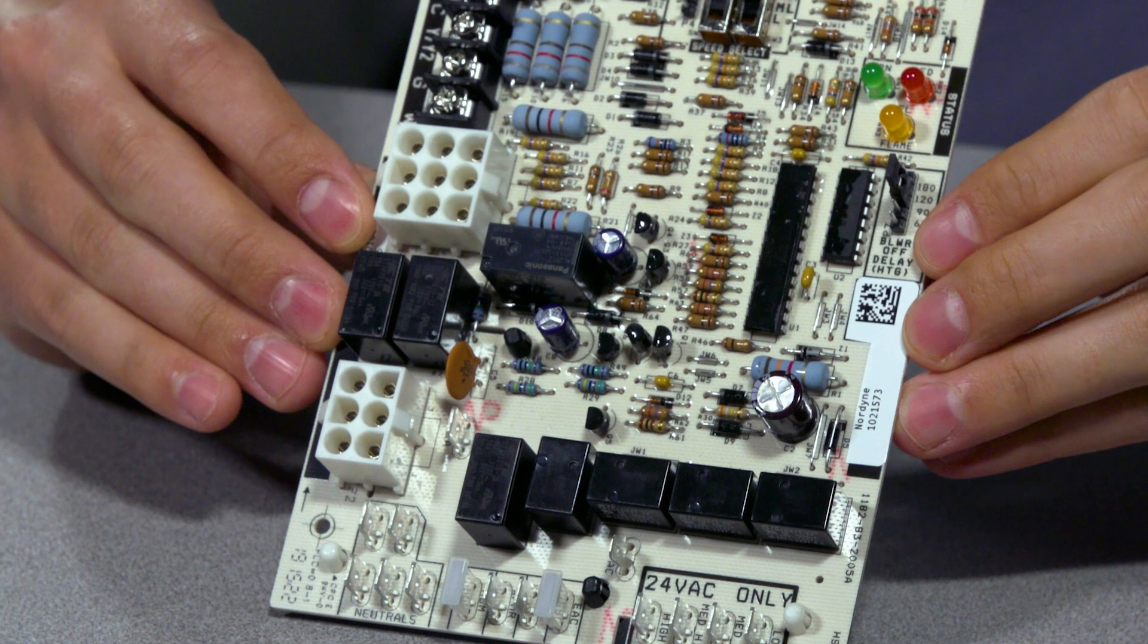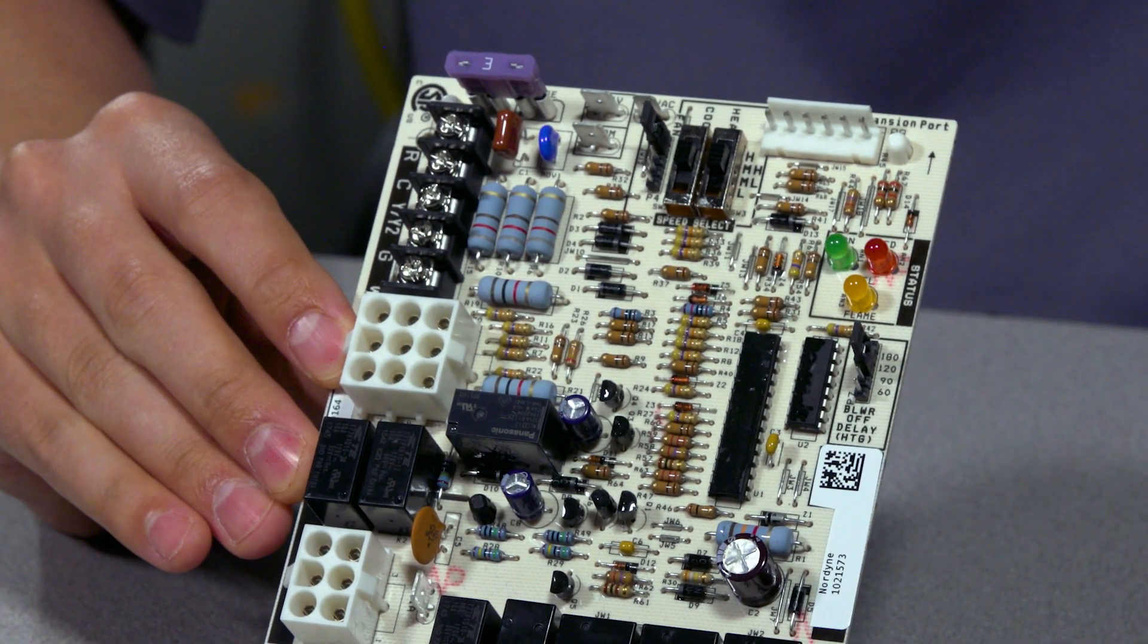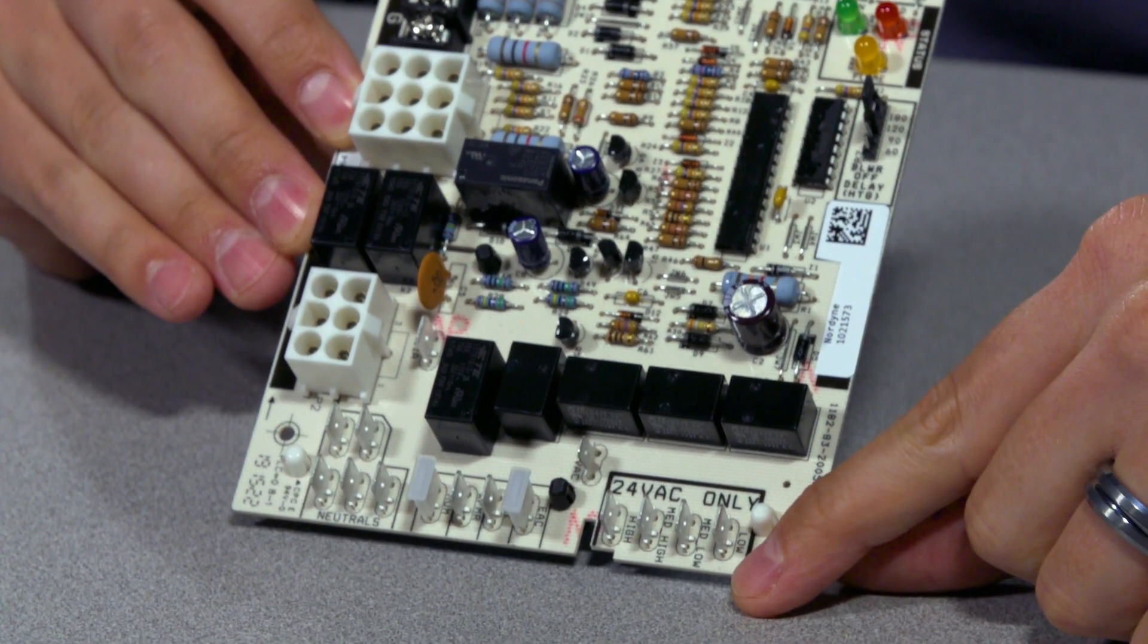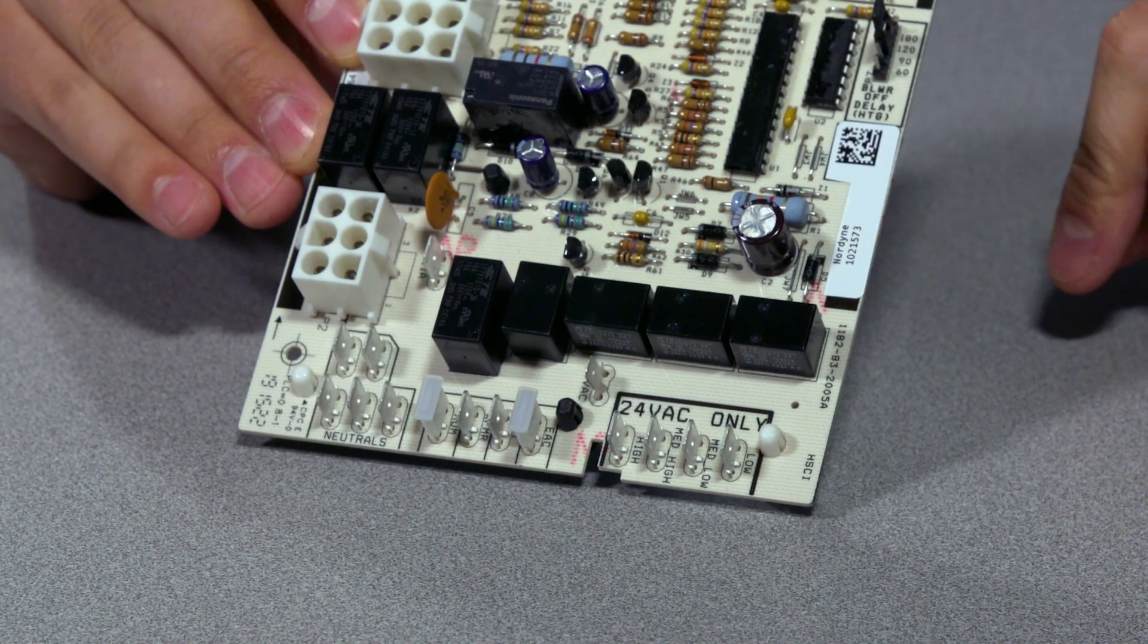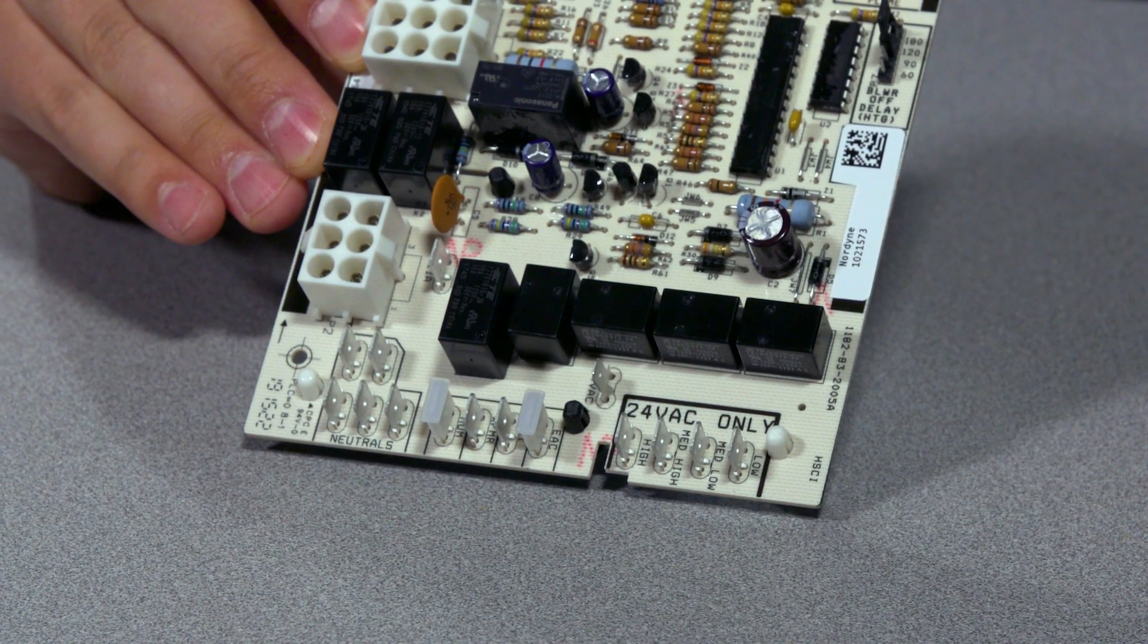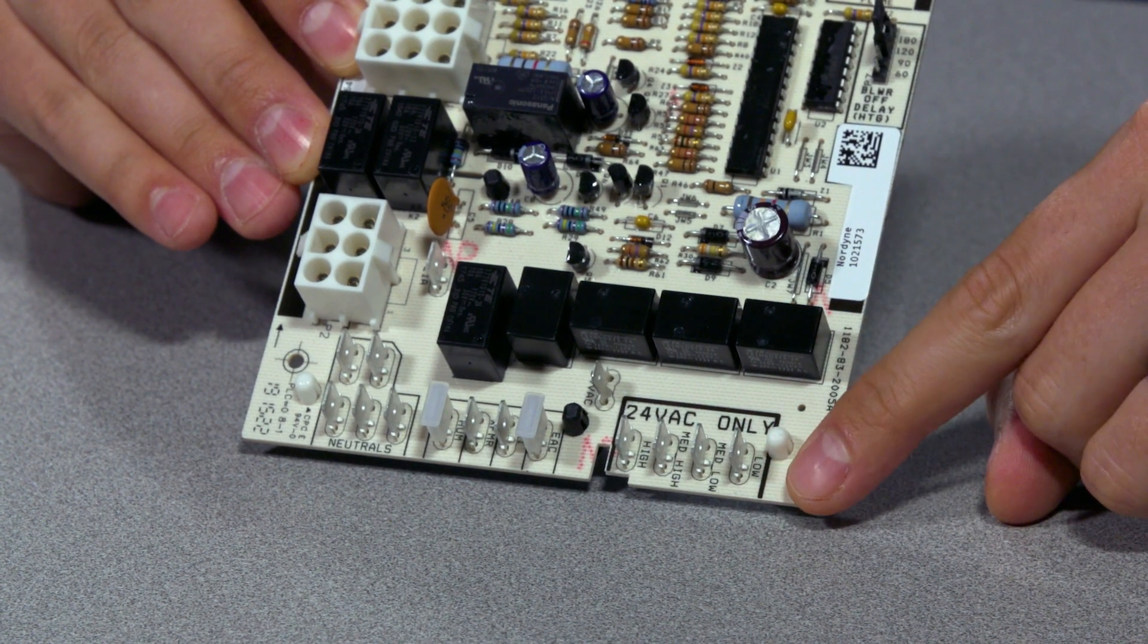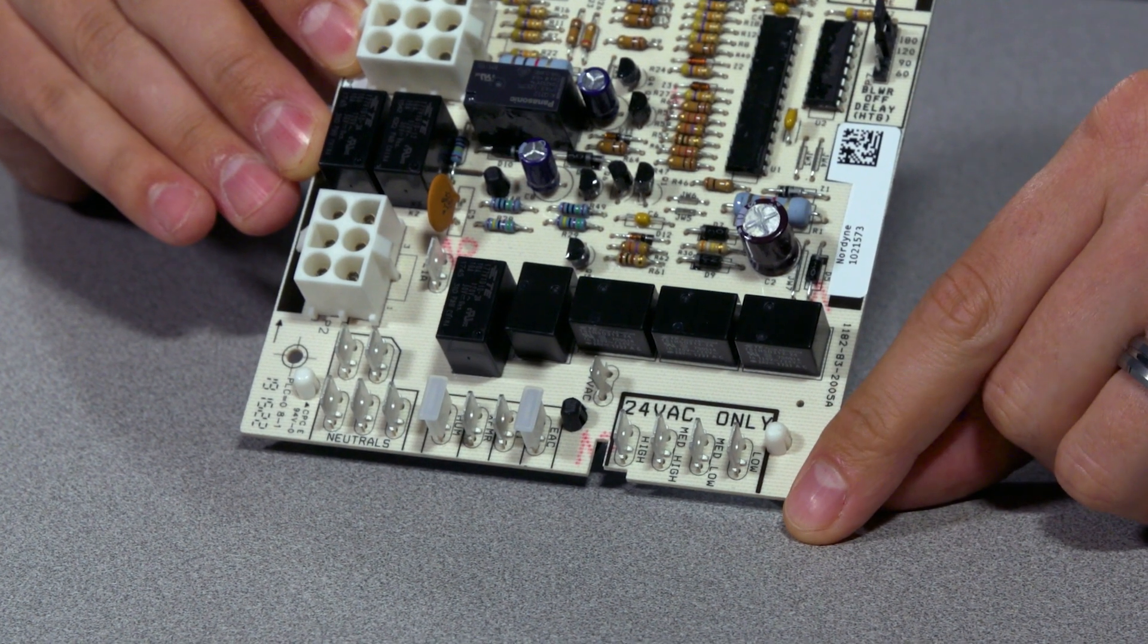So what I have in front of me here is the new G7 board. At the bottom of the board here, traditionally on the old one it was line voltage that was being outputted of the board. Now what we have switched to is this four pin plug down here is going to be a 24 volt VAC or AC current going to that motor.